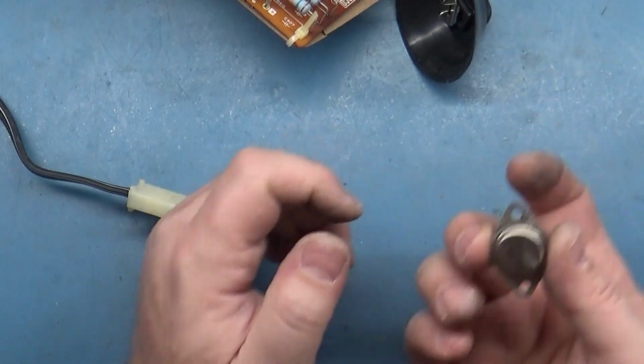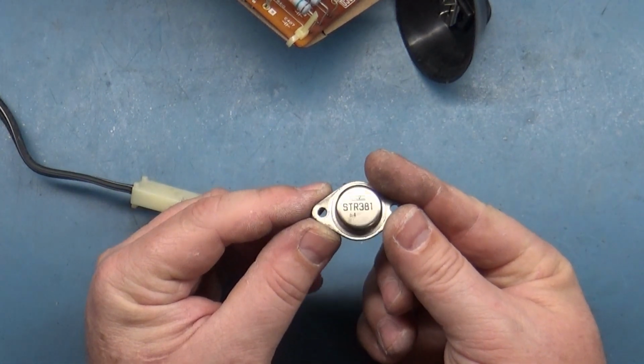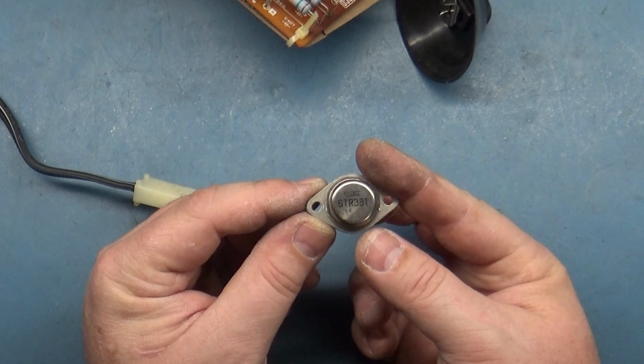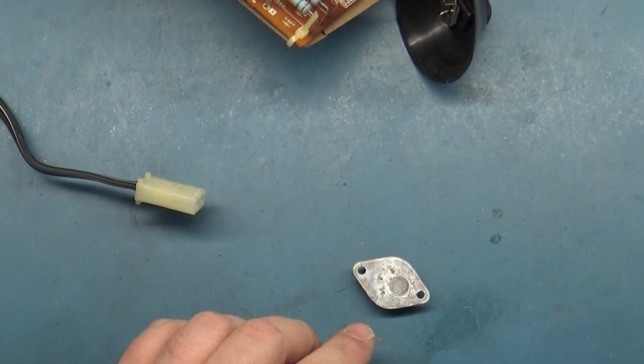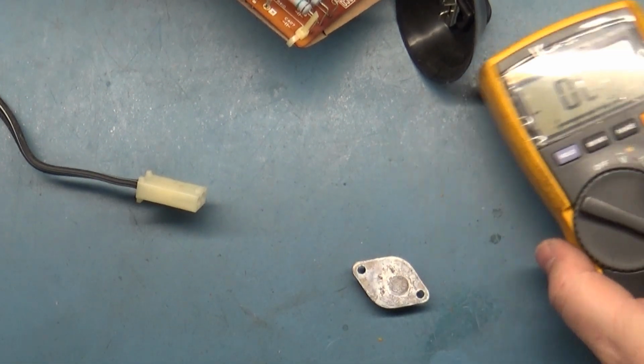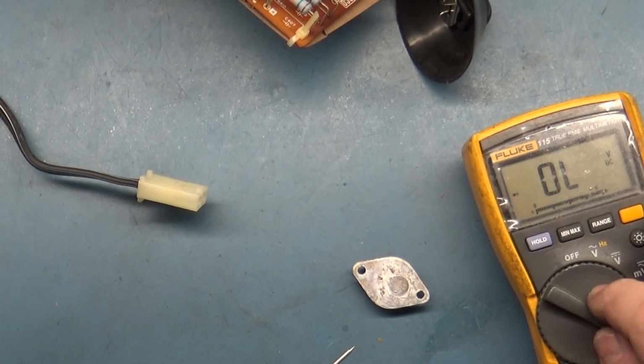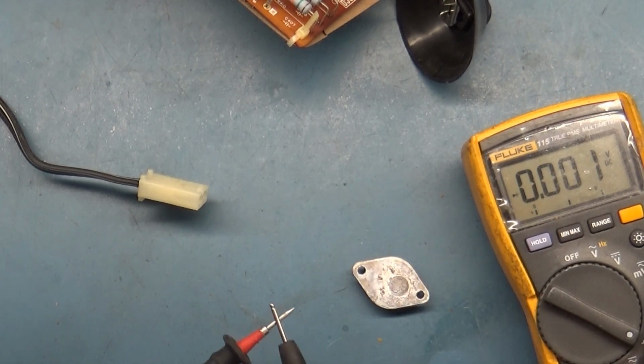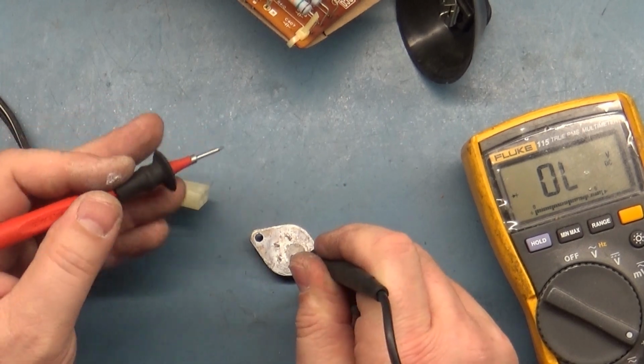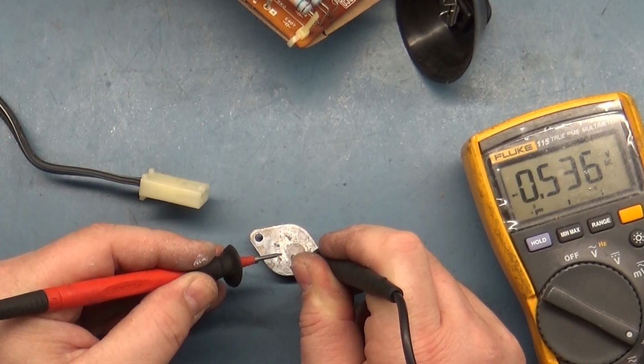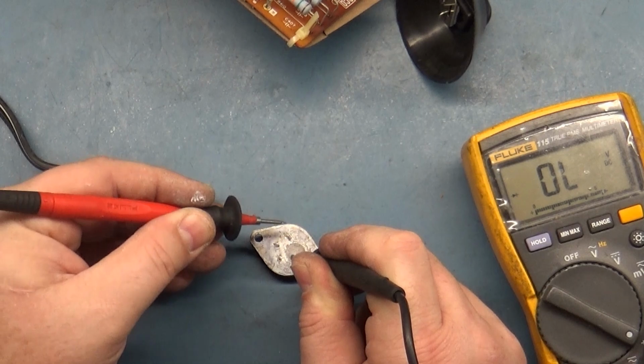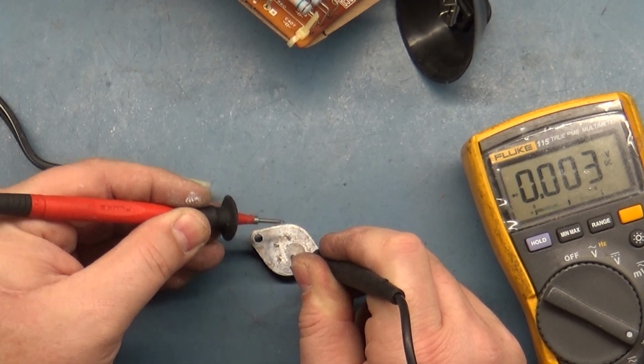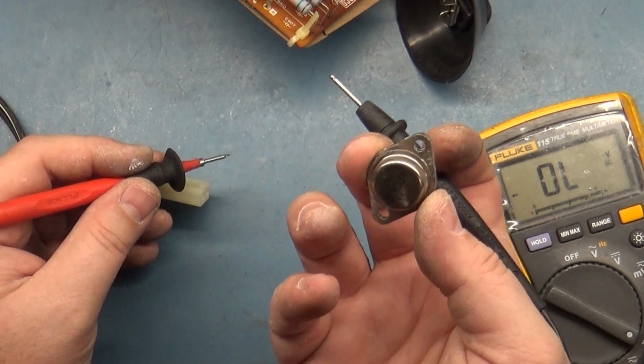So let me show you how to test these. Your STR3831 should not have any legs that short to the frame. If we get our meter here and go to diode mode, we touch the frame and touch this leg — there's our voltage drop. This leg, open. This leg, shorted. You don't want that.